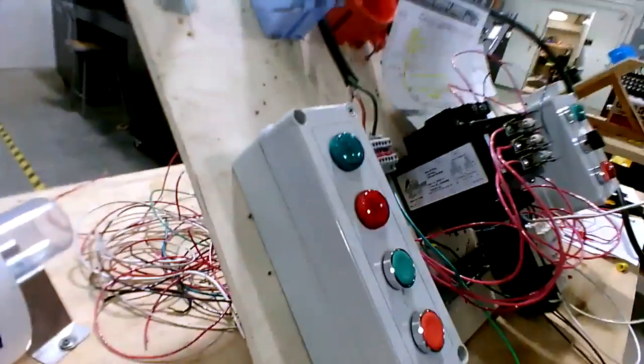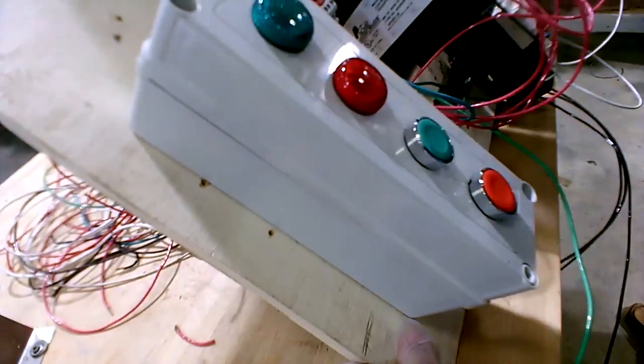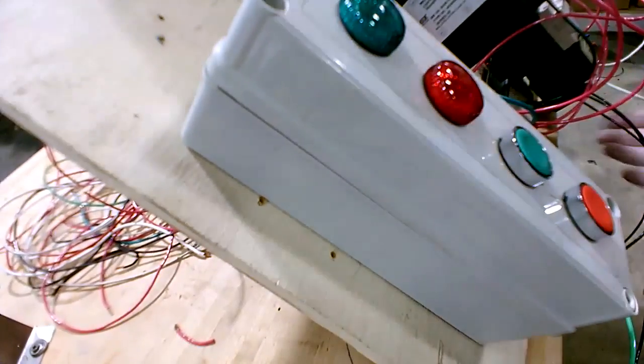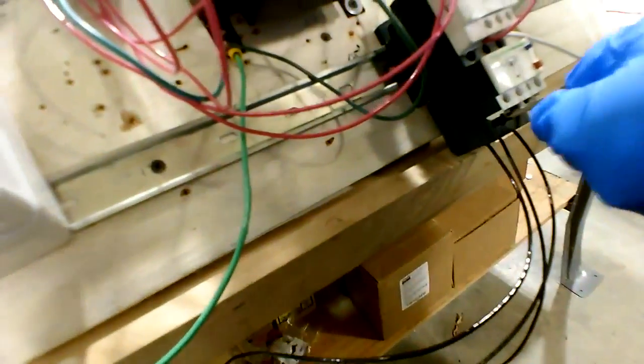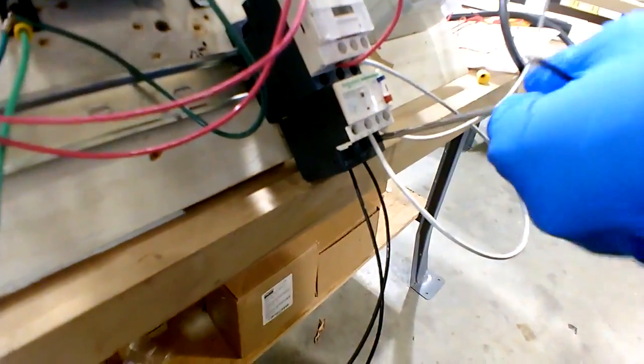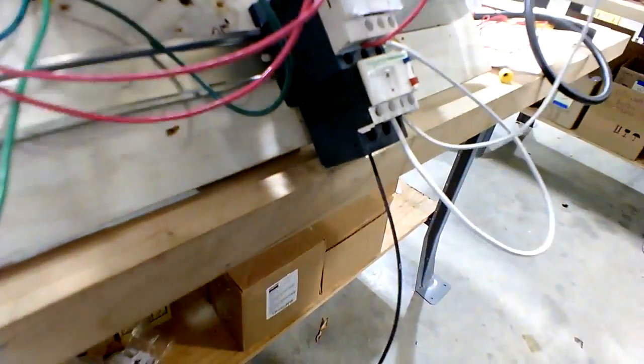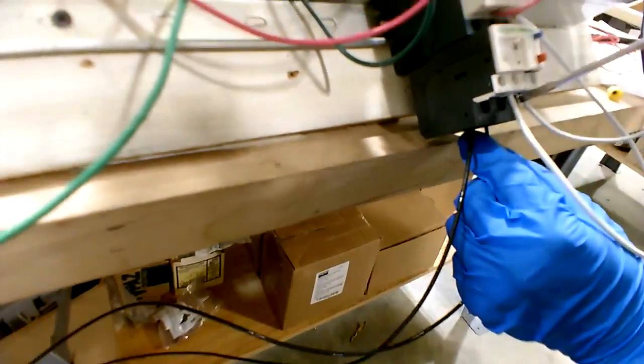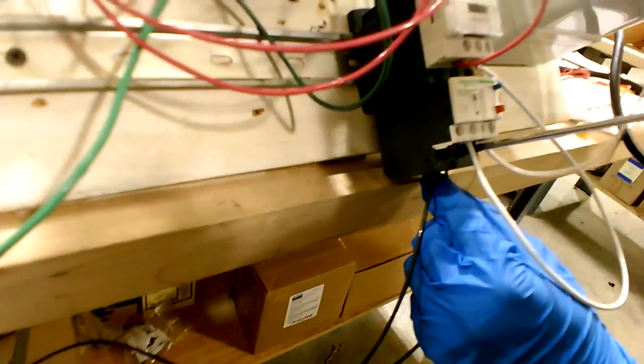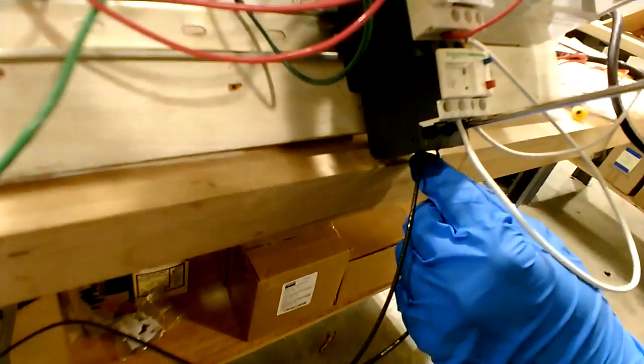So you can go ahead and now pick any two and reverse them. We'll bring it out this way, it'll make it easier. I'm going to switch 1 and 3. That's most common, do 1 and 3. Those of you watching, you always make sure that the circuit's dead. You verify it with a meter. He's going to the easiest spot to get to flip two of those phases. And he did lock the power out. So lockout, tagout is mandatory.